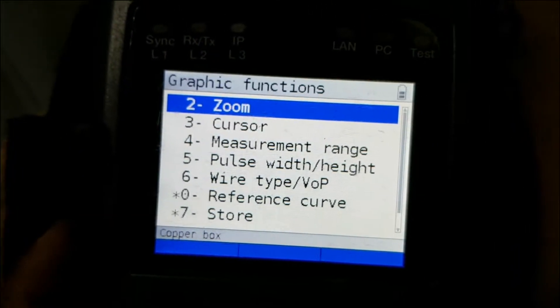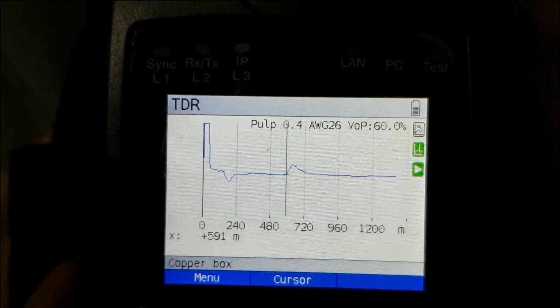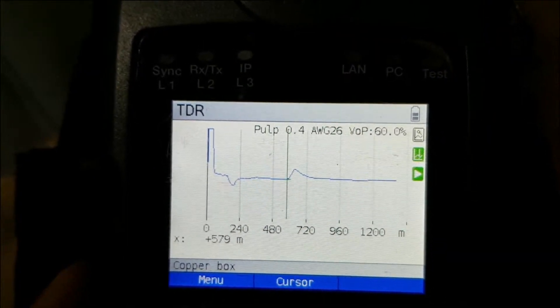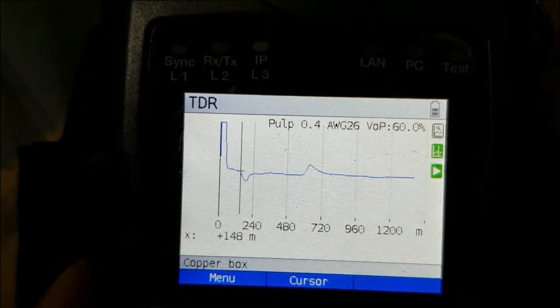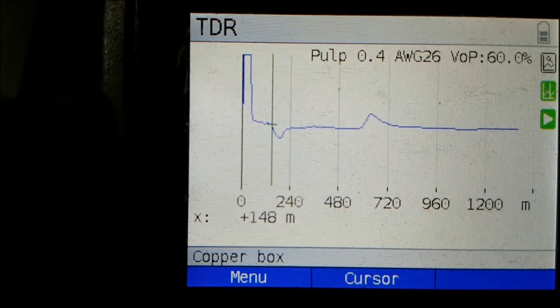So we'll use our cursor to see the exact measurement. This is 580 or 590 meters — the cable length. And we'll move the cursor further to the downside. This is 148 meters. So there is no problem from this end of the cable up to 148 meters. After 148 meters there is an issue in the cable which is grounded.